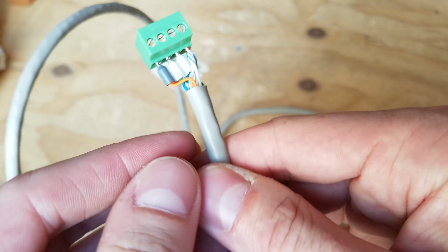On the opposing end, I have the same layout: orange and brown for the 5-volt positive, orange stripe and brown stripe for negative, and the green and blue switched for transmit and receive on the opposing connector. You'll notice I only have 2 stripes connected on the ground here, whereas I have all 4 stripes connected on the side that goes into the Watchmon. It was explained to me that you only want these connected on one side of the connector.